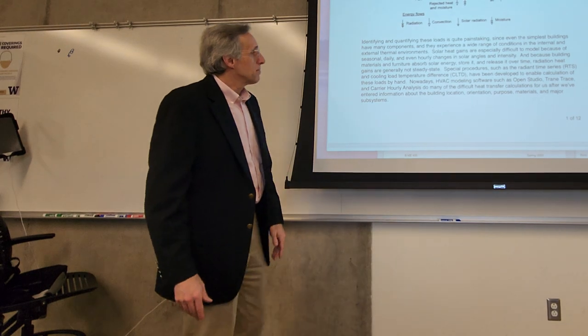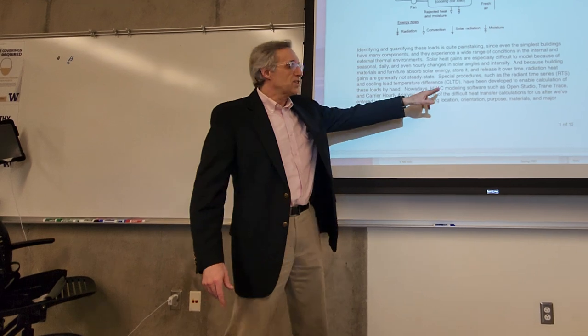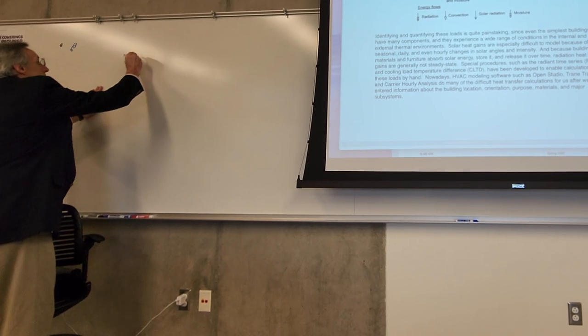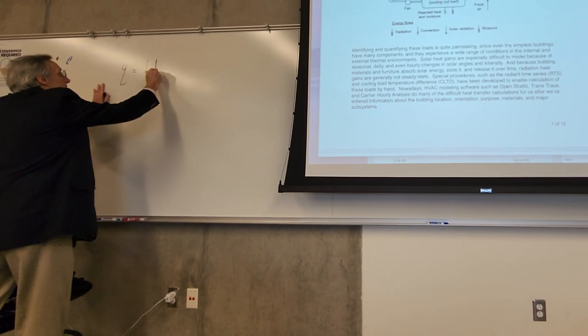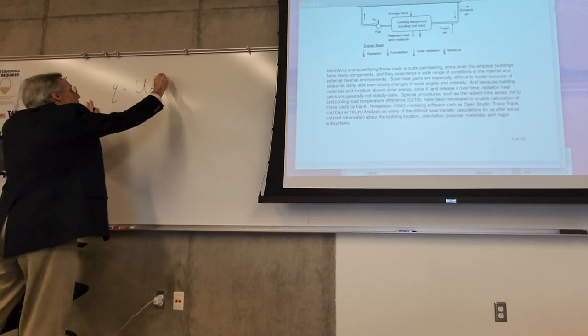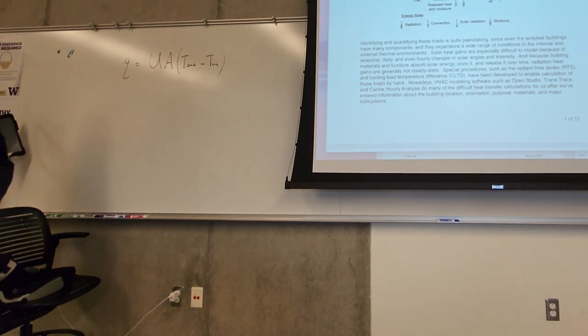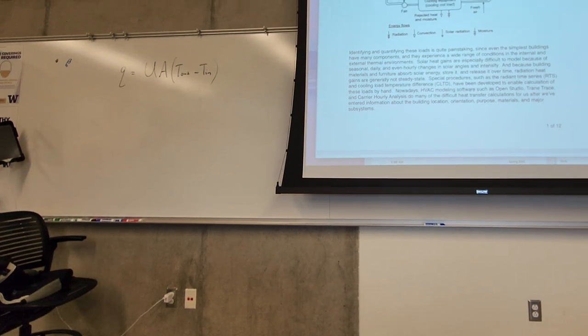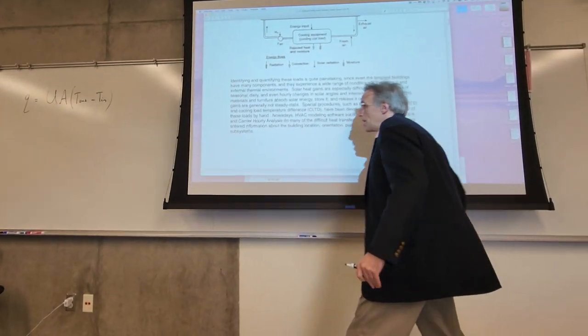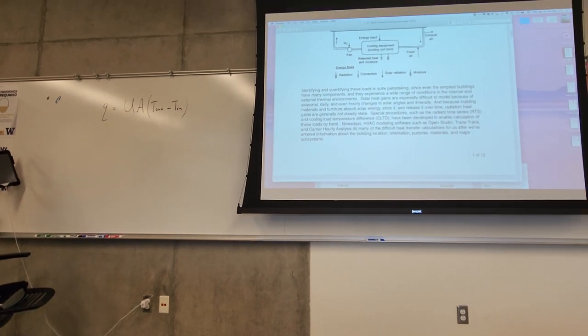The Cooling Load Temperature Difference (CLTD) method is a really handy method. Every heat transfer calculation becomes Q = U × A × CLTD, where U is the heat transfer coefficient and A is the area. Normally that would be conduction and convection only, but with CLTD we can even model instantaneous solar radiation. However, we'd miss a huge part of the solar heat gain because it is not instantaneous.